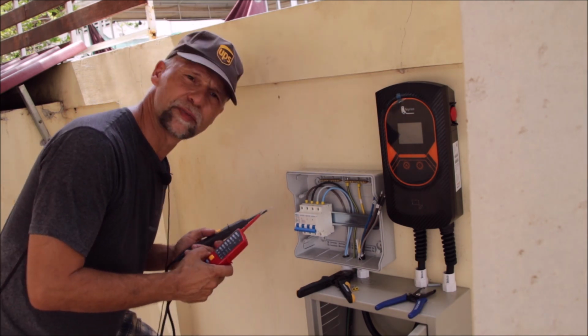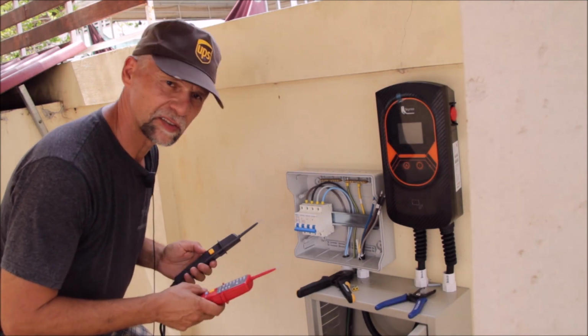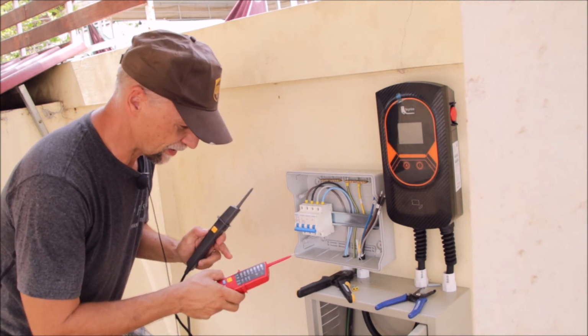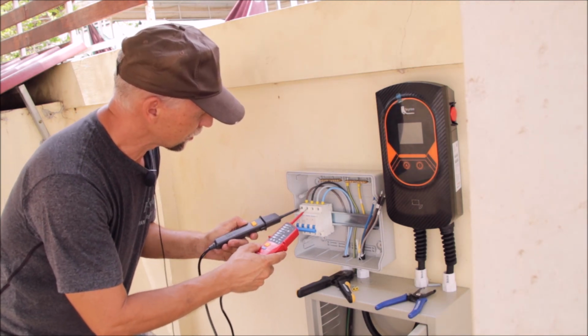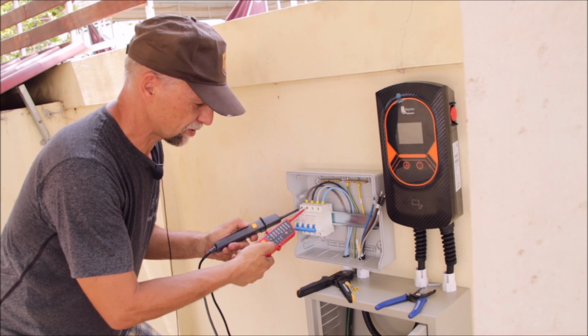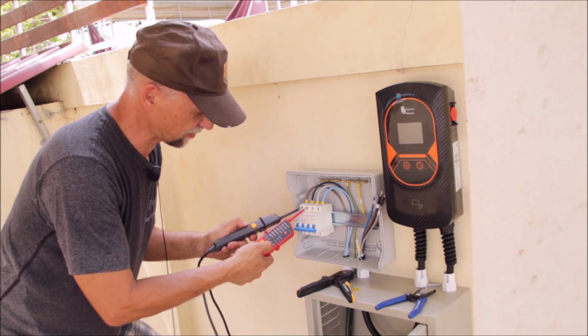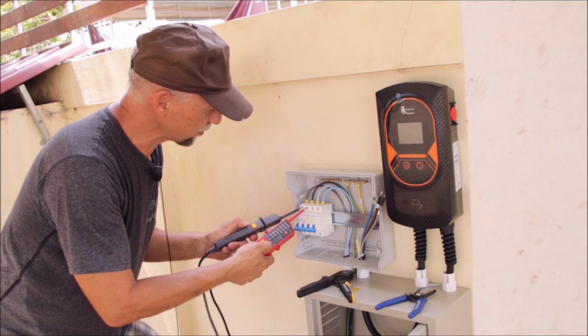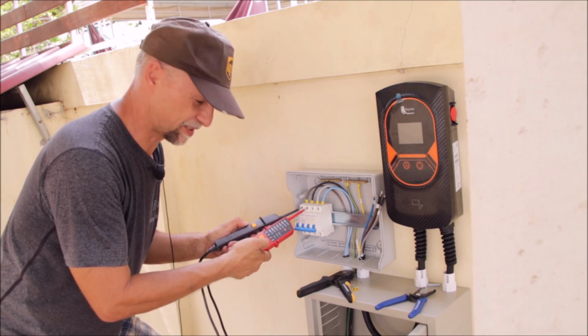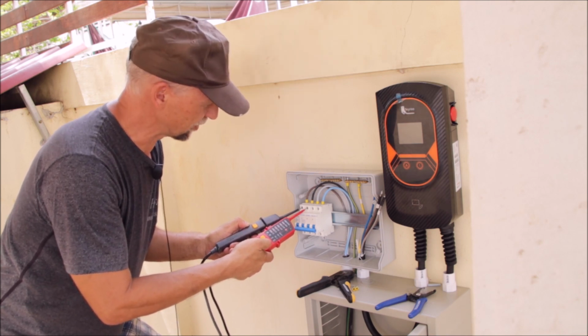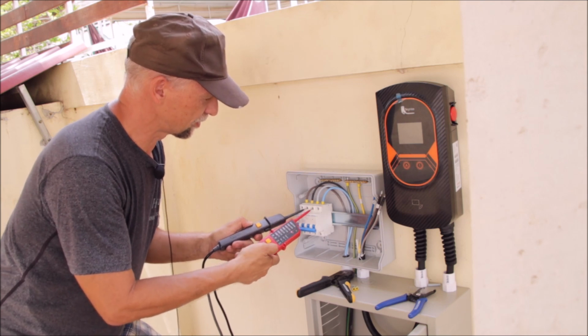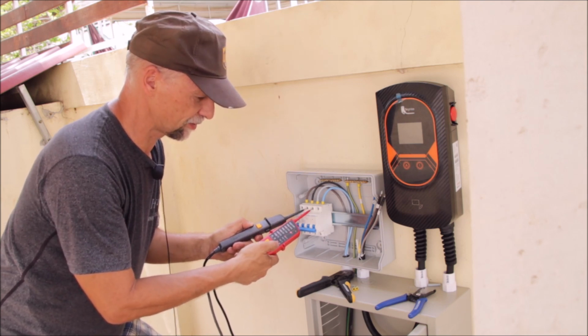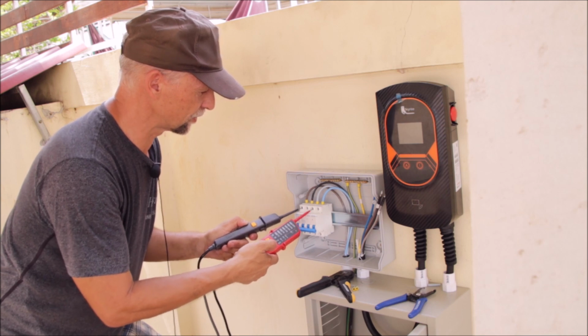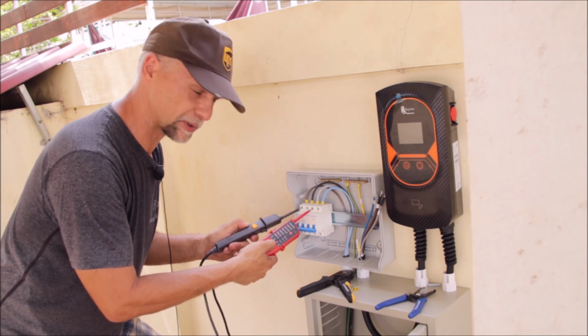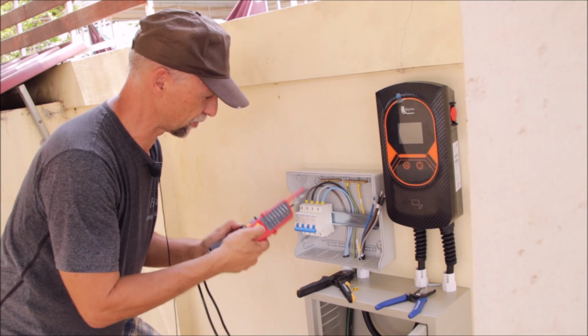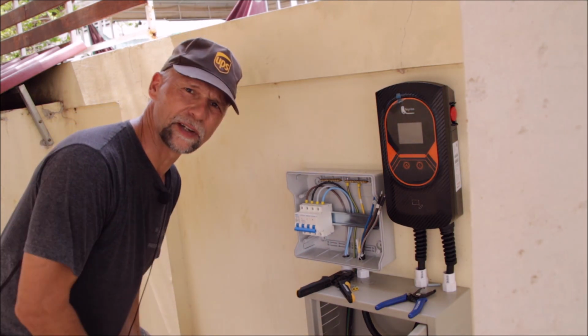We can also check the field of rotation of the 3-phase system. So this probe is marked L1, this L2, and when I hold this to L1, L2, I also see here an arrow, and this time it's shown at the right. So we have right field of rotation, which is the standard at installing 3-phase systems. So we can also go between phase L2 and 3, still right. If I would hold now L1 to L3, then it's going to the left, so it's a wrong field. I would have to turn my probes. Okay, so everything is fine here.